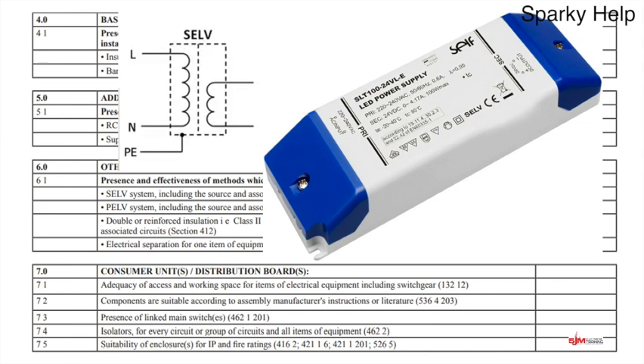What does it effectively do? Well, we're separating from earth. Okay, some people call it safety, but it's separated extra low voltage. So the idea is that obviously on the supply side, the transformer is earthed at the star point. So if we touch the line conductor on anything on the supply side, we'll get an electric shock, as probably you've experienced. But if on the output side of a SELV transformer, not only have we reduced the voltage to a much safer level, i.e. below 120 or below 50 volts AC, but if you did touch the live conductor, there is no connection to earth anymore. So you could be grabbing hold of a metal pipe, grab hold of one of the line conductors, the positive conductor, and nothing would happen.